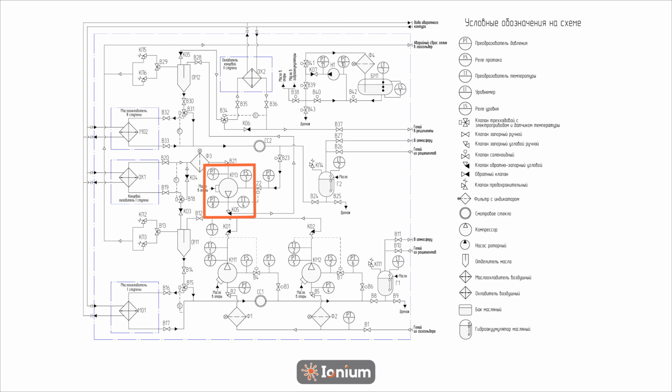Helium cooled to about 16 degrees Celsius at a medium pressure is sent for compression into the second stage screw oil-filled compressor at position KM3, where, due to a change in geometric volume between interacting screws, it is compressed along the rotational axis to a pressure of 24 bar. The second stage screw oil-filled compressor at position KM3 shares the same technological characteristics as the first stage compressors. Oil is injected at 2/3 from the suction window.